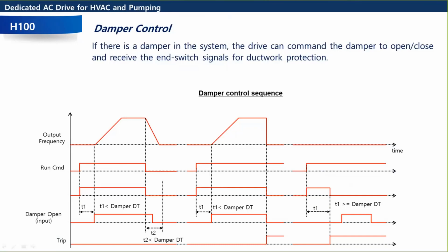So how it works is you give the drive a run command, and then you give it a damper open input. And then there's the delay time, so the damper should be open, let's say, in 20 seconds. If we don't hit that end switch, so we don't get an input saying that the damper's open within 20 seconds, the drive will trip out saying something's jammed up, something's frozen, something mechanically is wrong. But if it does open in time, then it's just going to start running. Okay, so you'll see your output frequency run like normal.